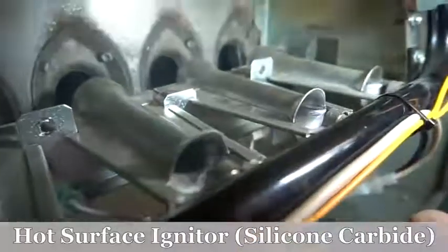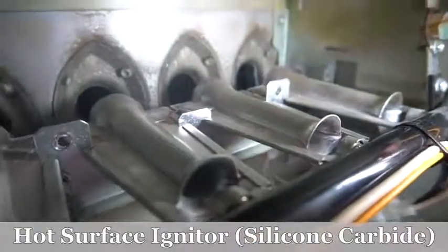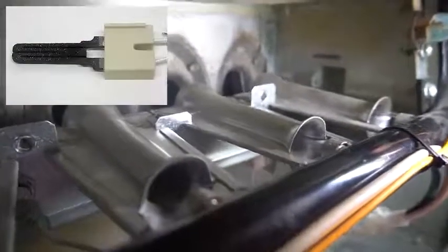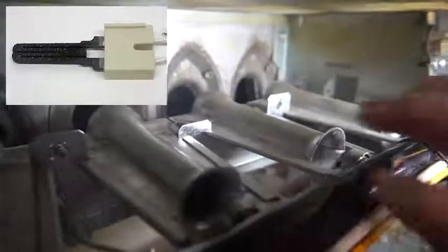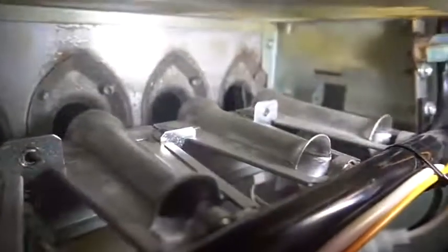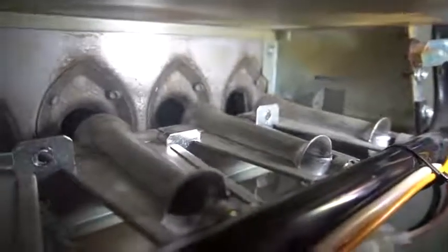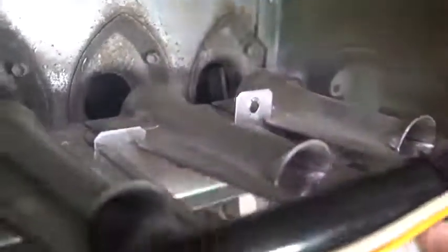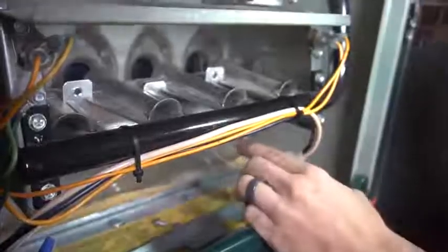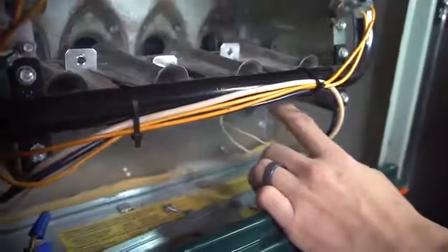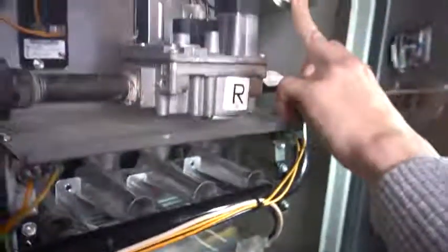And then right there, that sparkly thing is an igniter. Different furnaces will have different ignition sources, or basically what lights the gas. It can be a spark igniter. The most common is a hot surface igniter like I have right there. Or you might have an intermittent pilot. And a lot of times you'll see a plug like this for hot surface igniters with 2 wires going to it. So in my case, I have a hot surface igniter. So after the inducer motor turns on, the pressure switch is closed.